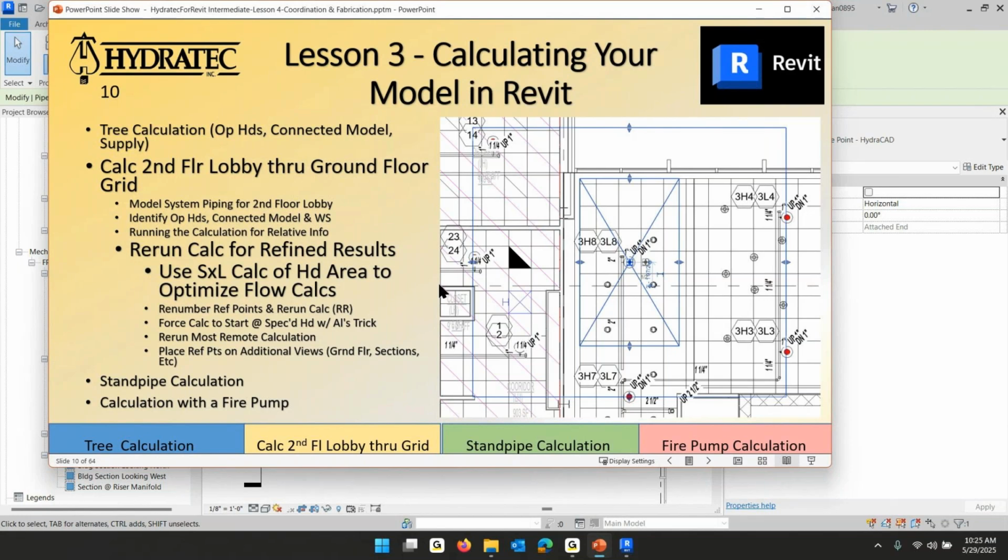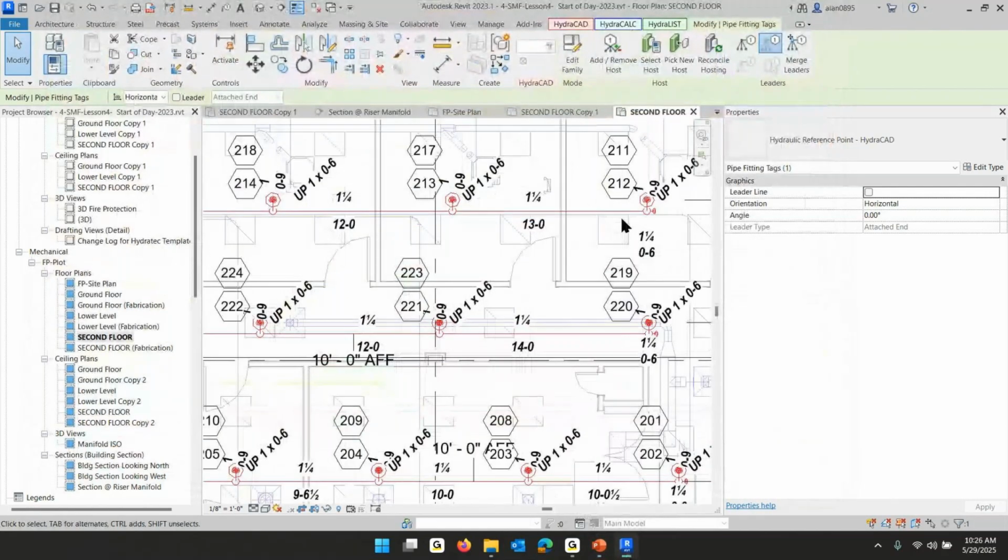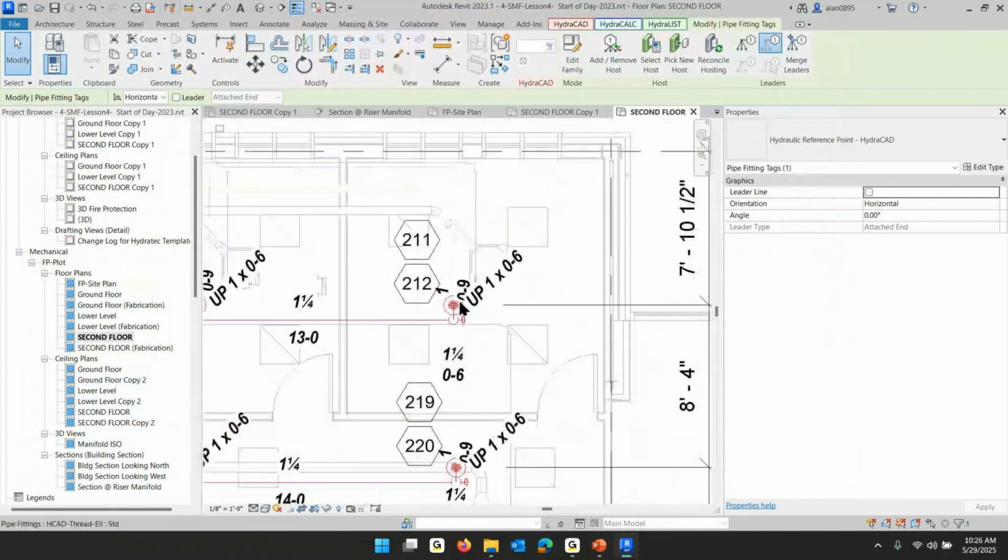And if while they're installing it, they need to move ahead a little bit, and they know to stay under 14 by 14, they can move it anywhere they need to make it work. However, that might be more of a tax on our pipe sizing than is necessary. So the first thing I'm going to do is say, let's measure the required area of that sprinkler, and let's consider using that instead of the 196. And I guess, Tom, I'm going to keep you in the hot seat for a minute if you're up for it. All right. How should we figure the coverage area of this sprinkler?